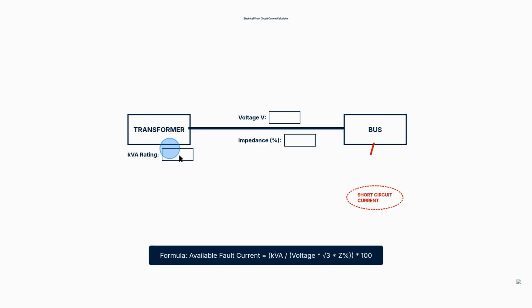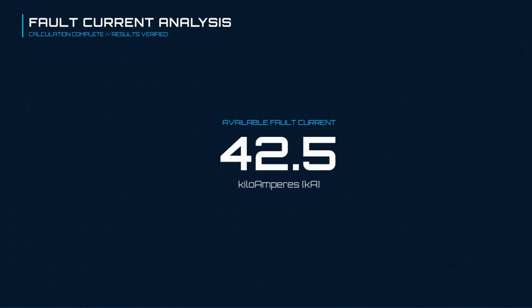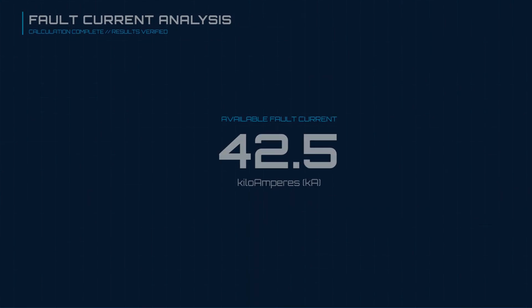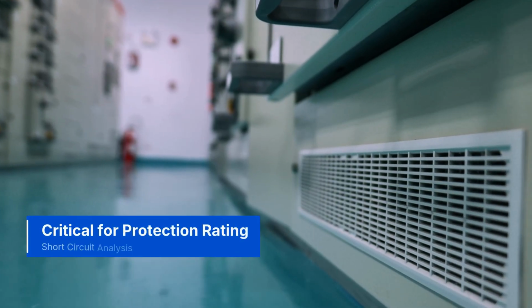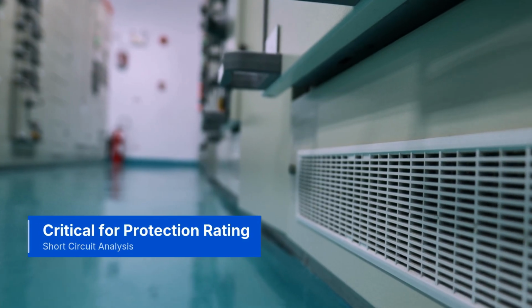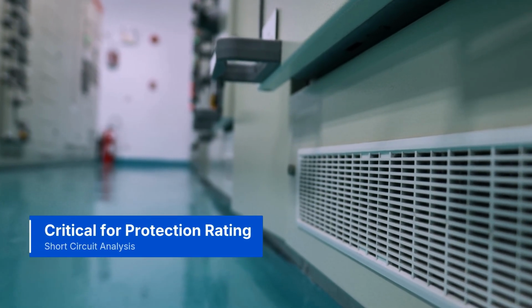For this demonstration, I'll enter 1000 for the kVA rating, 5.75 for the impedance percentage, and 480 for the system voltage. After clicking Calculate Short Circuit Current, the calculator processes these values to determine the fault current characteristics. The results show the maximum short circuit current that would flow if a bolted fault occurred at the transformer terminals.